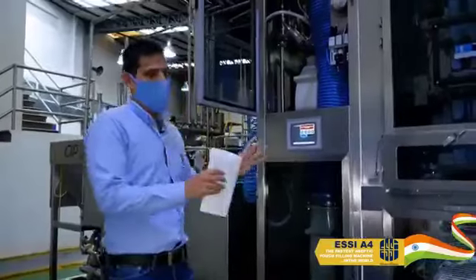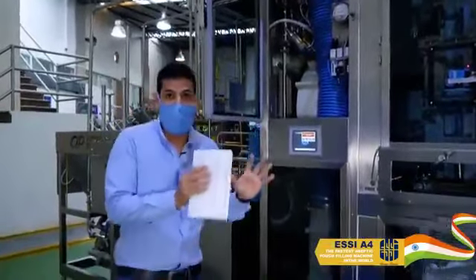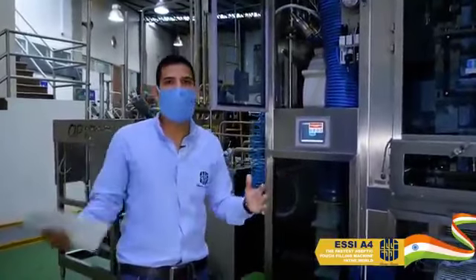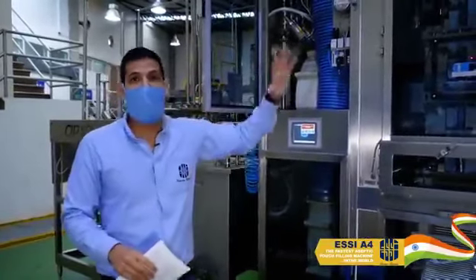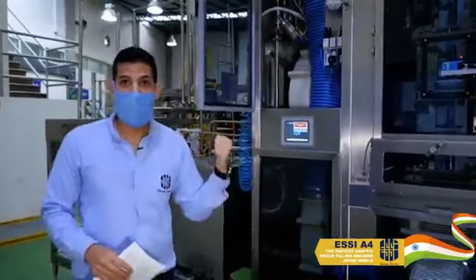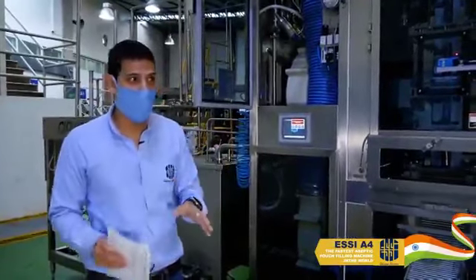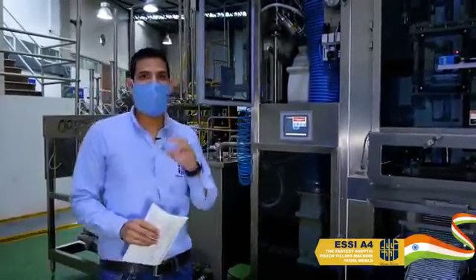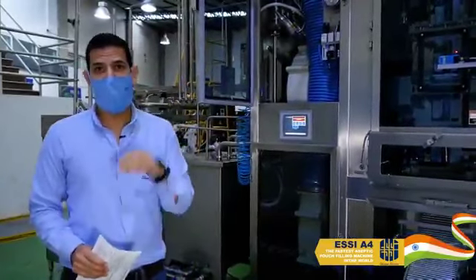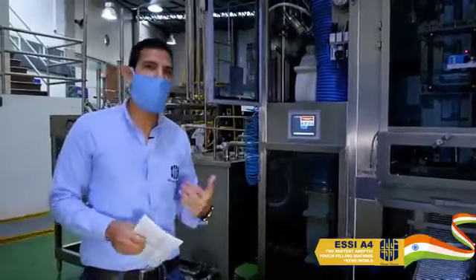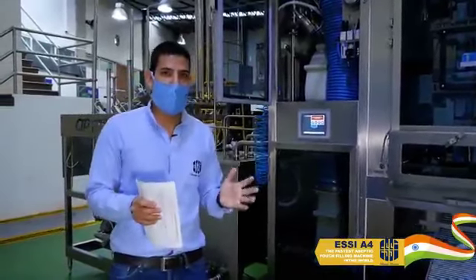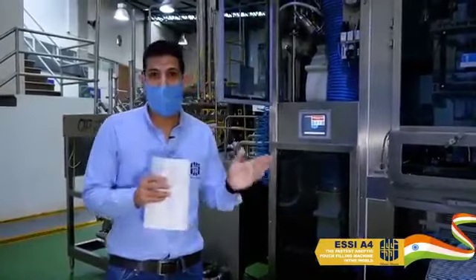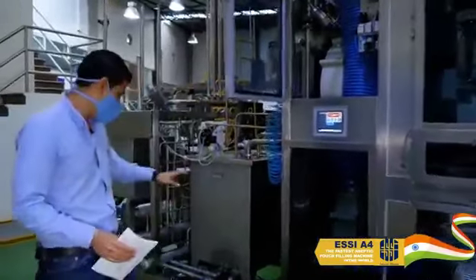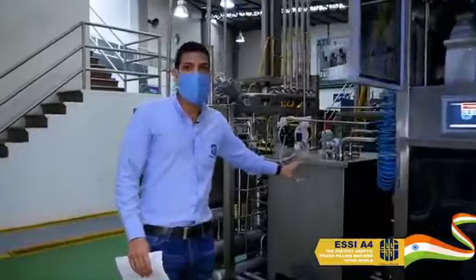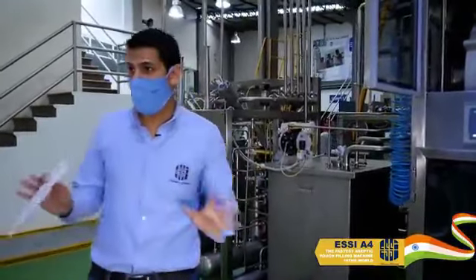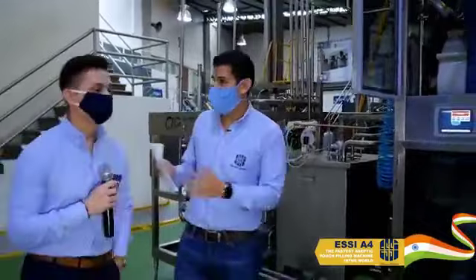With this, first we have the cabin pressurized with a little bit just to make sure that nothing goes in, and we use laminar flow to make sure that when we open the door there is not going to be any issue or problem. And the third one will be the sterilization of the plastic. And how do we do that? With peroxide. We use peroxide with 35% concentration and a temperature between 40 to 45 degrees. And where do we do that? Here. That part is the peroxide tank. And that's it. These are the two systems of the sterilization.